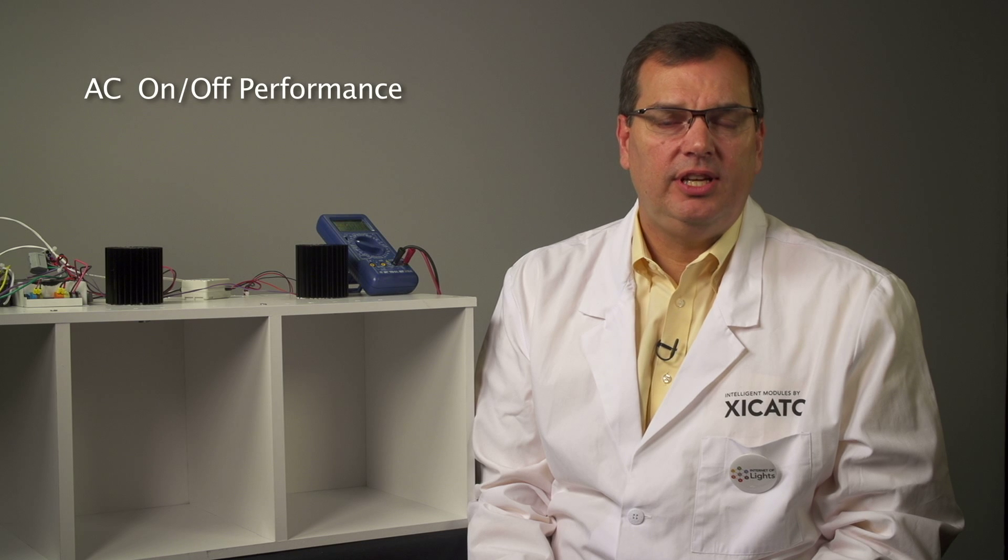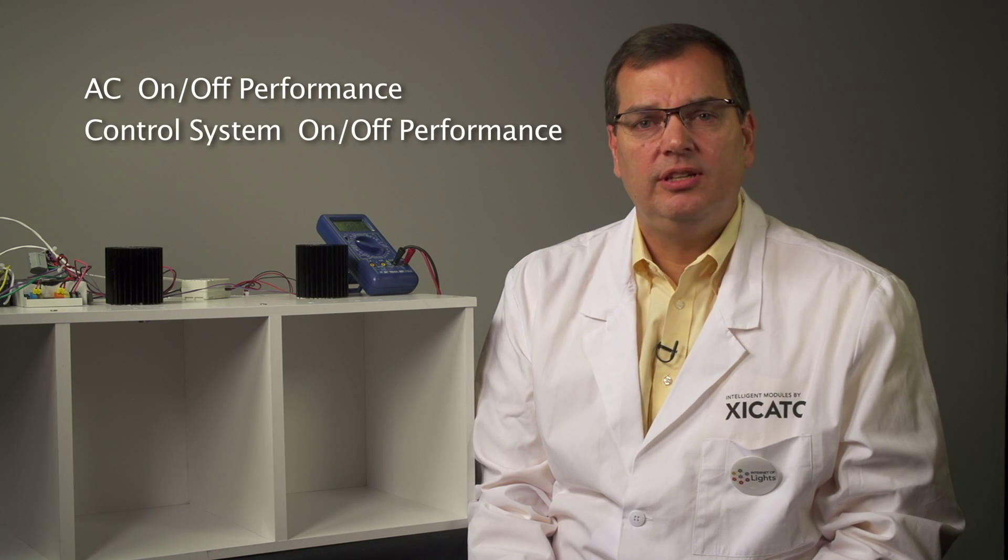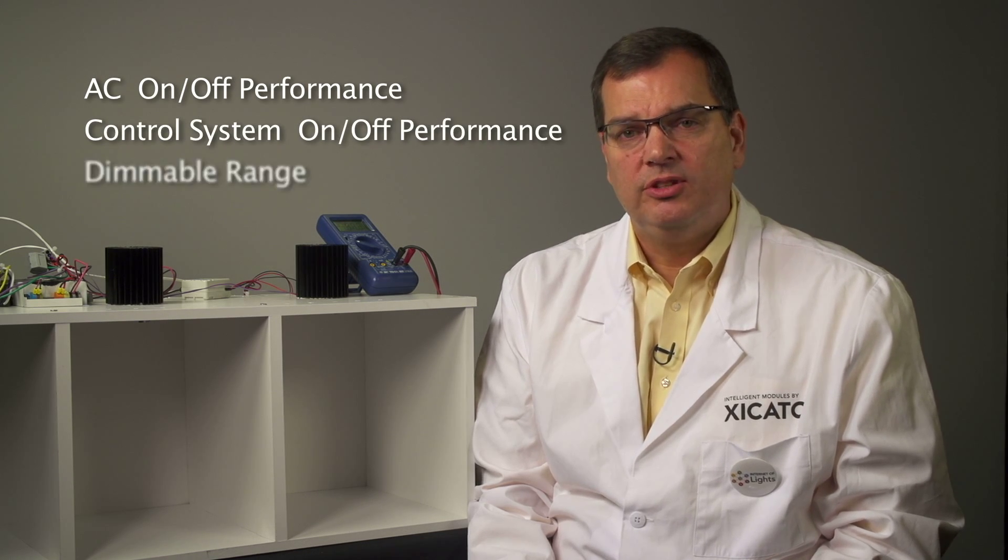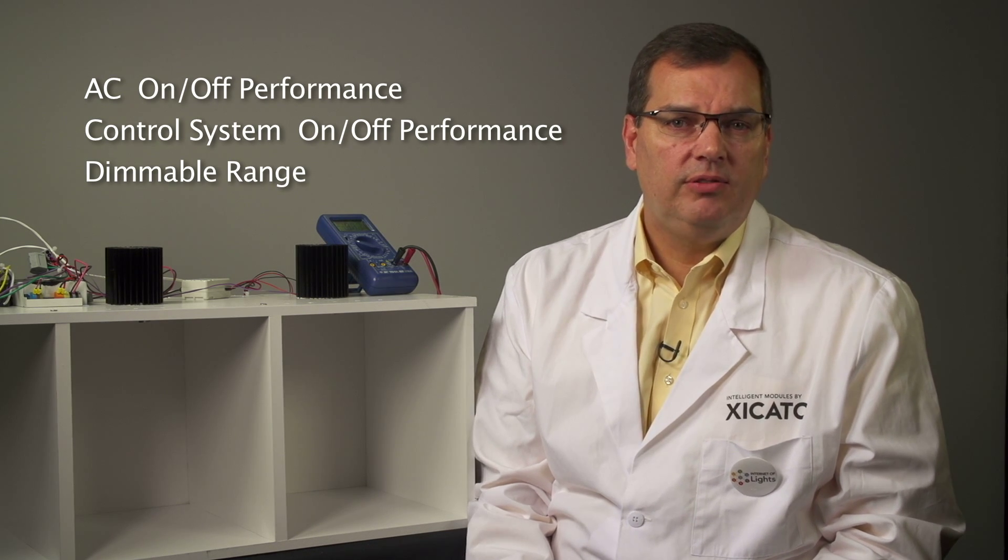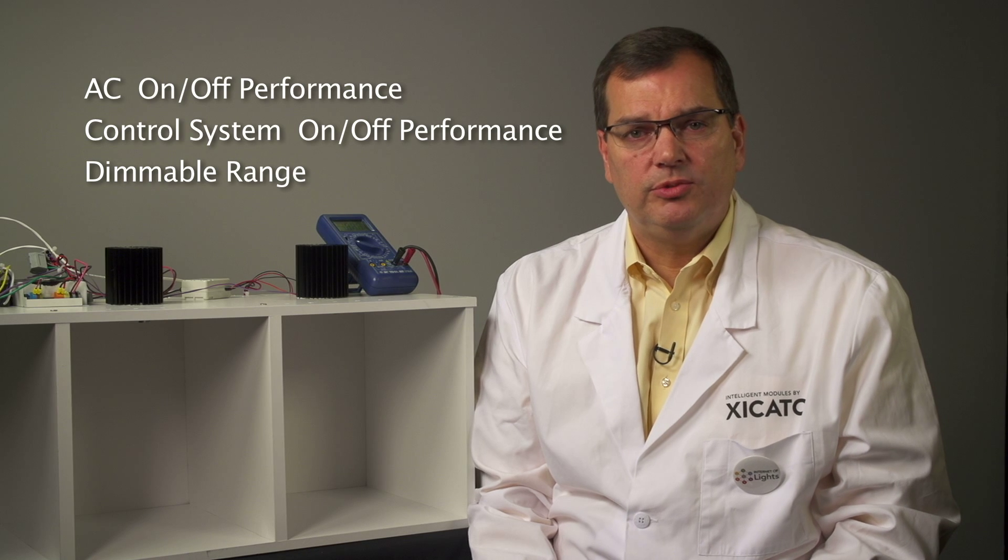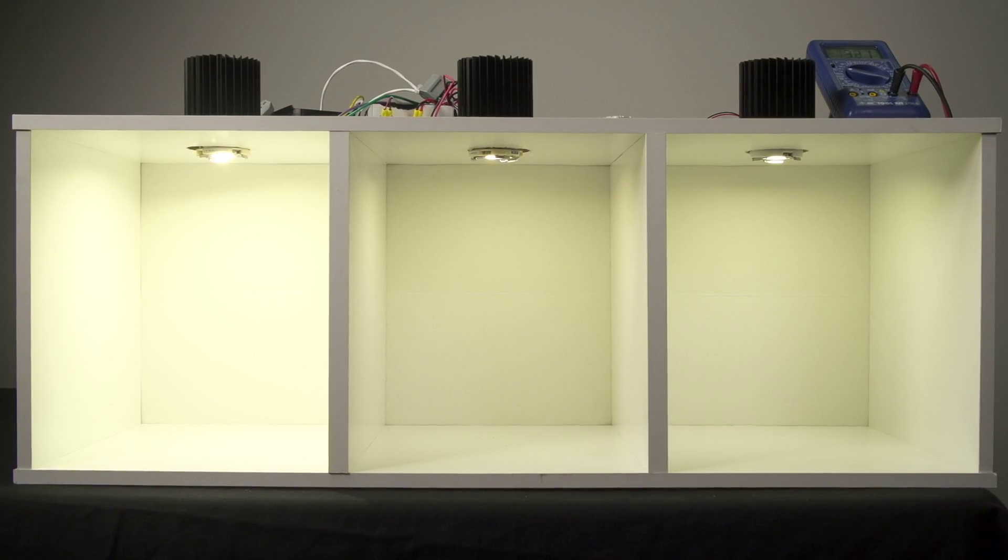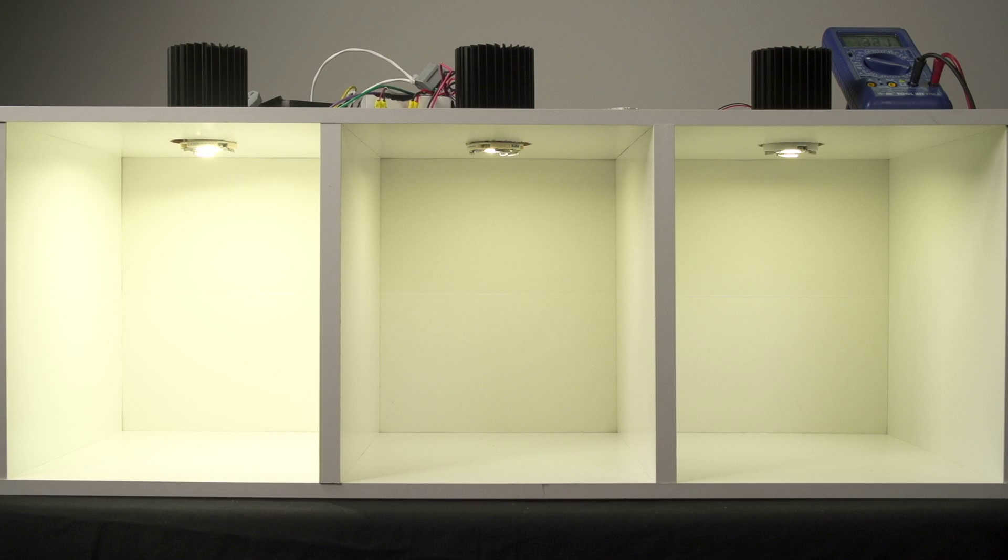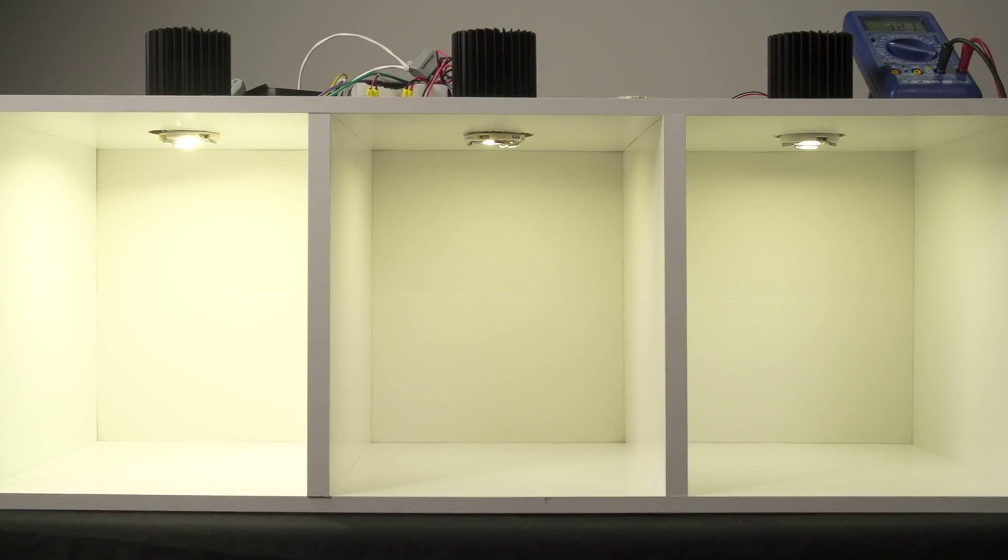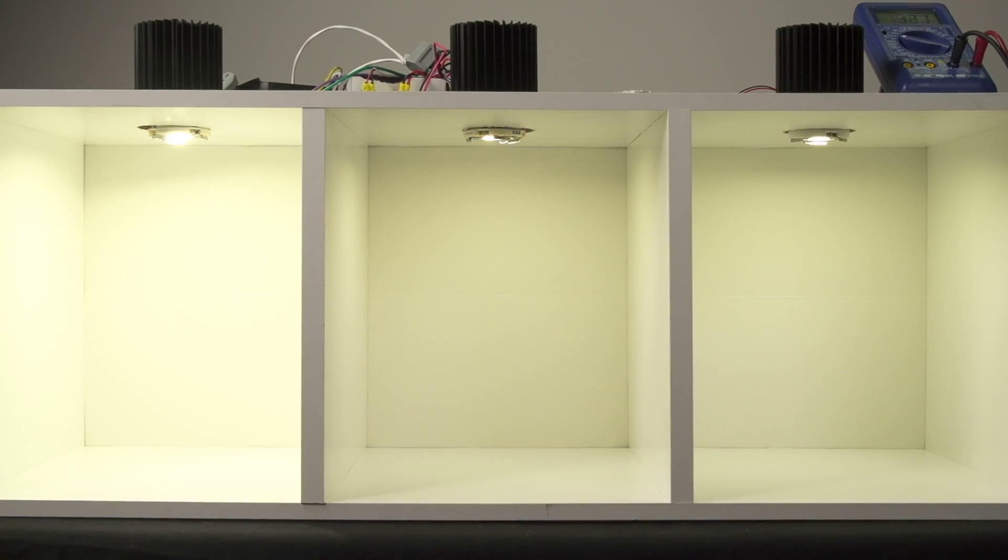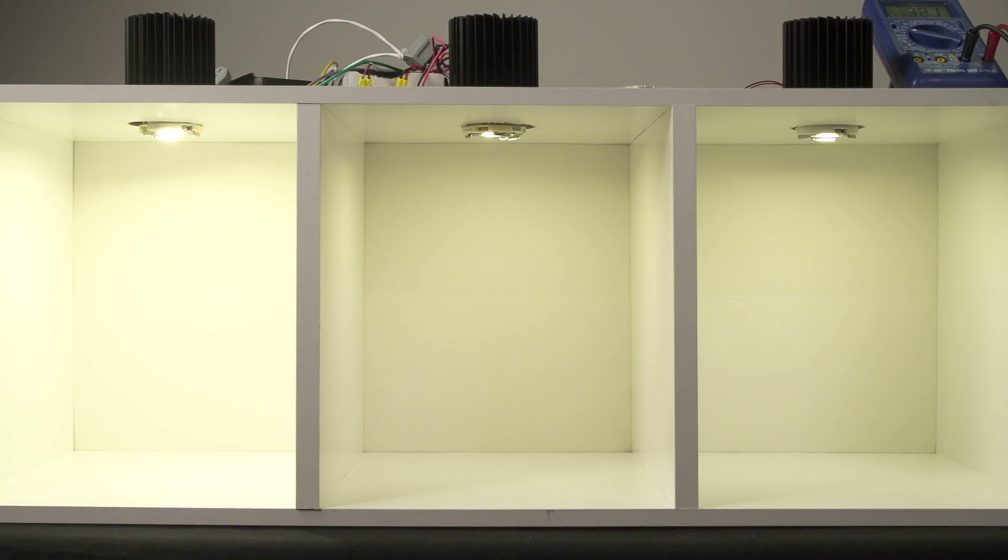So now you know three things to look for when evaluating LED dimming solutions. First is AC on-off performance, second is control system on-off performance, and the third is dimmable range both at the driver level and in terms of control system response. These are all important things when looking at LED dimming and being satisfied with your overall dimming solution. You don't have to settle for poor quality LED dimming. The solution is here with XIM.